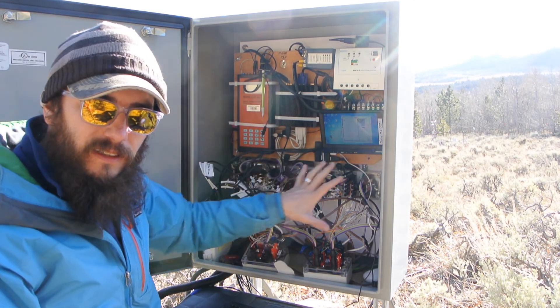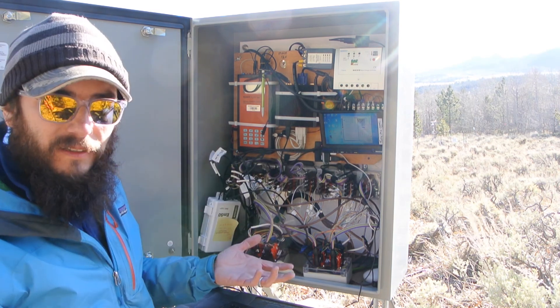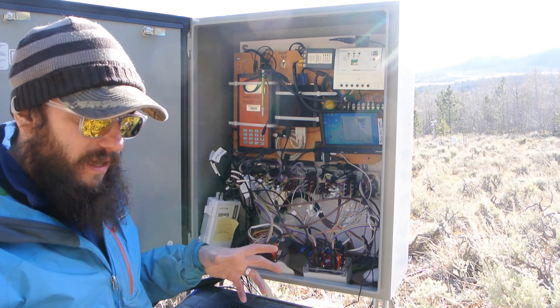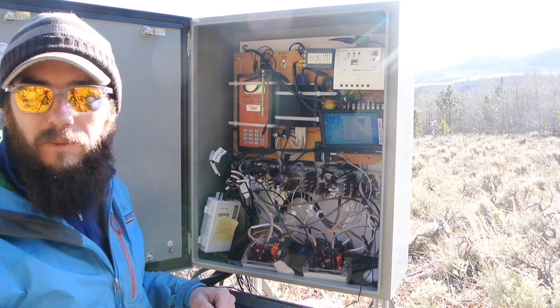And then there's a whole bunch of wires, and these wires basically connect everything to the ground. All we're going to do is download the data here, and then we're actually going to go and check to see that the instrument is still set up properly and connected to the ground as well as possible.